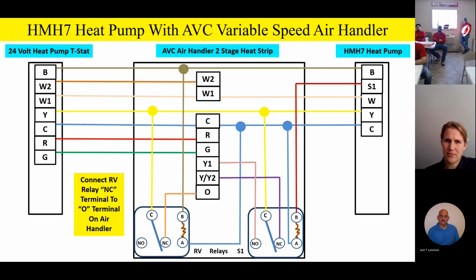Earlier at the beginning of the presentation, I thought you said that O being energized would be heat mode and it defaults to cool mode. I love the way you're thinking. And that's exactly correct. And so don't confuse the BO selection on the thermostat for heating mode on the outdoor unit reversing valve. This has nothing to do inside.